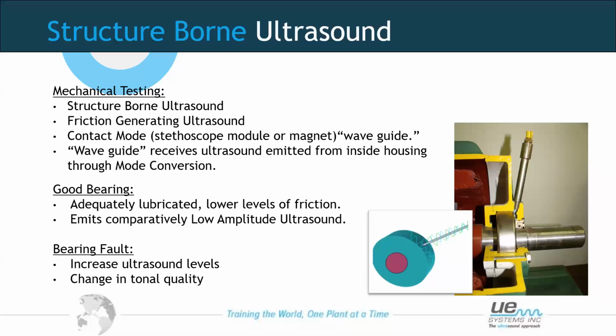If we have a bearing fault or a potential problem occurring, we're going to start seeing an increase in the ultrasonic emissions. But also, we might see a change in the tonal quality. So it's not always just about the level of ultrasound being produced, it's the quality of the ultrasound being produced as well. If we start to hear repetitive impacting sounds, or knocking sounds, we might even hear a change in the sound wave up and down, maybe indicating some sort of imbalance or misalignment, for example. The characteristics of the sound could change.